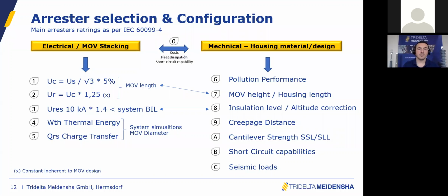The first step is to look at the continuous operating voltage, which is UC, the phase-to-ground voltage that the surge arrester can continuously withstand over its service life. Therefore, you have a very basic calculation considering the maximum phase-to-ground voltage plus a safety margin to include some harmonics and to be on the safe side.